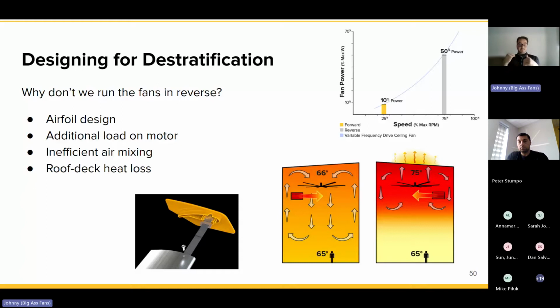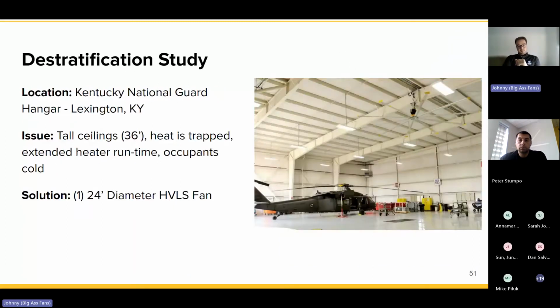Run it slow, use less power, so you're not running that fan as fast, and you're going to effectively push that heat to the ground where your people are, and like I said off the hop, where your thermostat is, which is almost as important, because that means your heating is not going to turn on as much. Okay. So quick study on the destrat side.